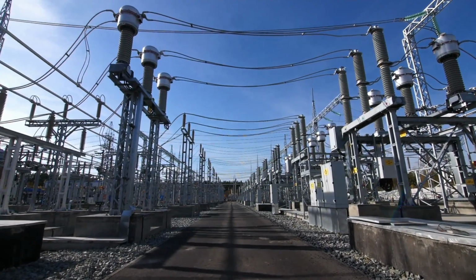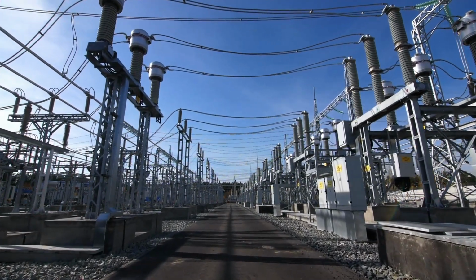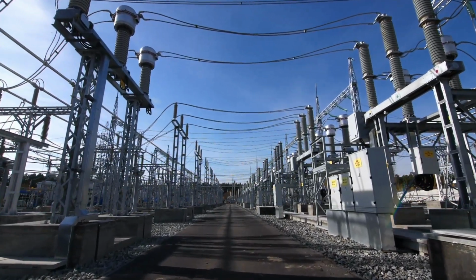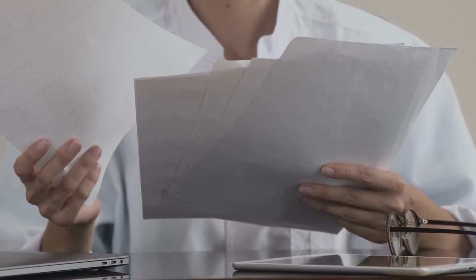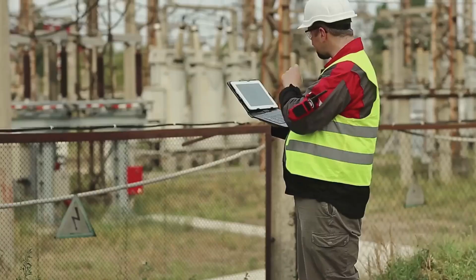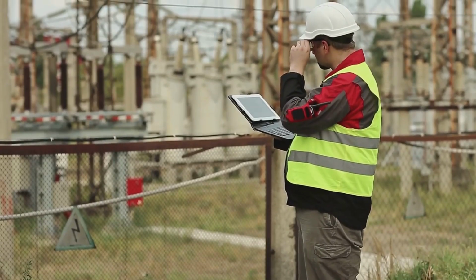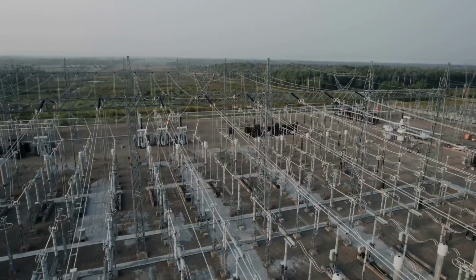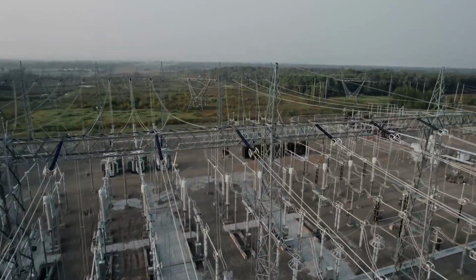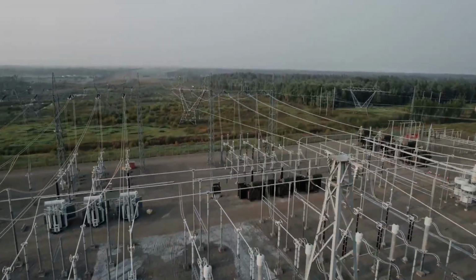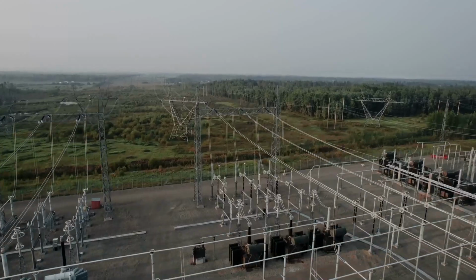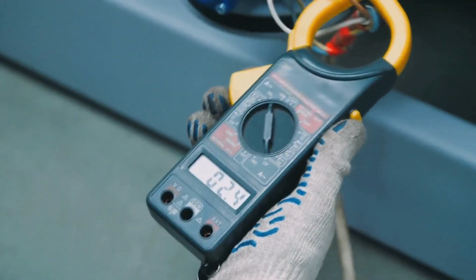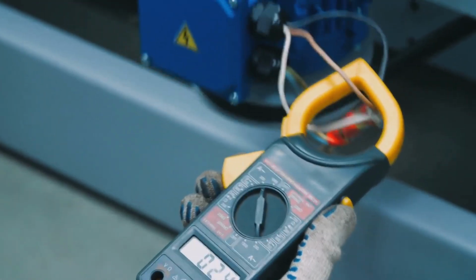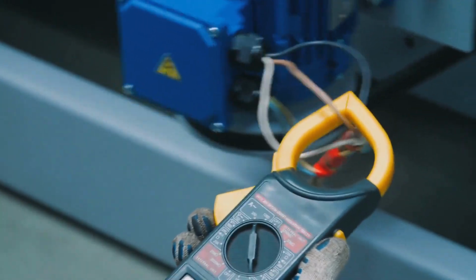Section 7 addresses how DERs must behave during both steady state and dynamic conditions to maintain power quality. Let's examine each clause through the FRT lens. Clause 7.1. DC injection limitations. DC injection into an AC grid can lead to magnetic core saturation in transformers and excessive heating in capacitors. IEEE 1547 limits this to no more than 0.5% of the rated output current.